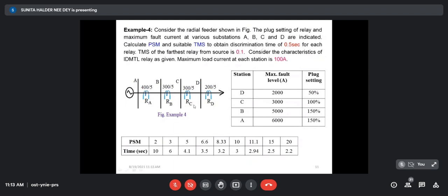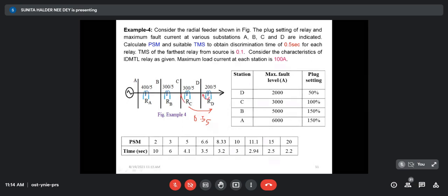That means if RC is a backup relay of RD, then RC will operate 0.5 second later than RD when operating as backup for station D. When it is operating as a primary relay for station C, it will have no delay. RC means this relay is near to station C, giving primary protection to station C. The IDMTL relay characteristics are given for all relays of the same type, and maximum load current in each station is 100 ampere.